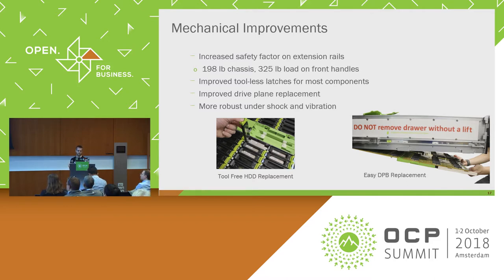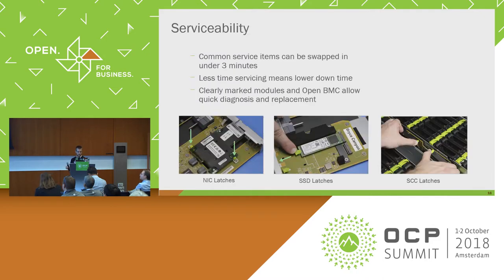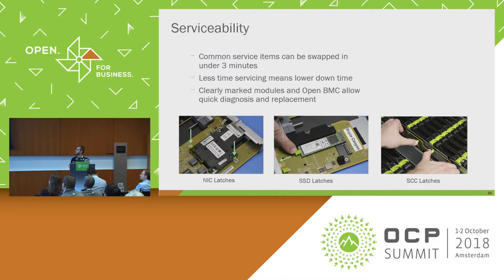We also improved robustness for shock and vibration during shipping, since we ship integrated racks fully populated. For improved latches: instead of screws or stiff push latches, we have little spring latches that hold the NIC down on the IOM, single-finger spring latches for the SSD, and the SCC latches were improved to allow quick serviceability without issues with strength or retention and without any screws — no tools required, which is great for data center technicians.